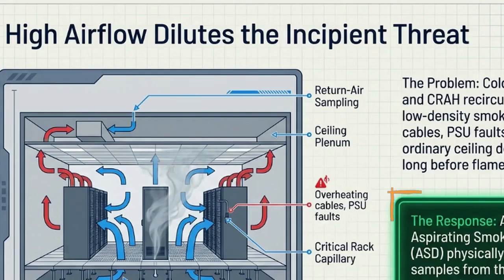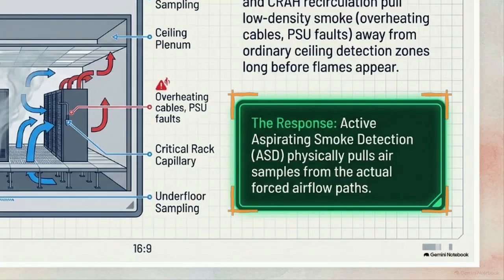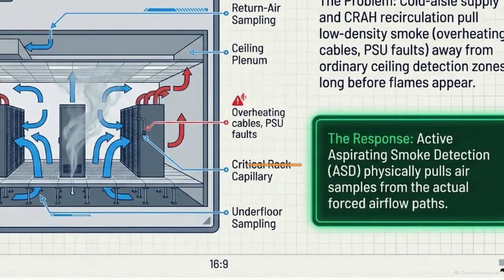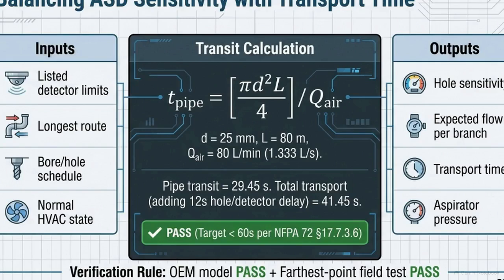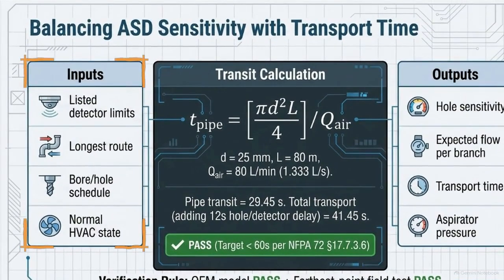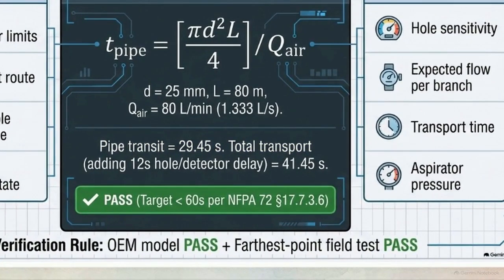The engineered response is active aspirating smoke detection, or ASD. Instead of waiting for smoke to rise, ASD uses a mechanical aspirator to physically pull air samples directly from the forced airflow paths, such as this critical return air capillary. But you can't just install ASD piping and hope it works. This transit calculation shows the strict mathematical verification required by code. Engineers must balance pipe length, bore/hole schedule, and listed detector limits to prove that air from the furthest point reaches the sensor rapidly.